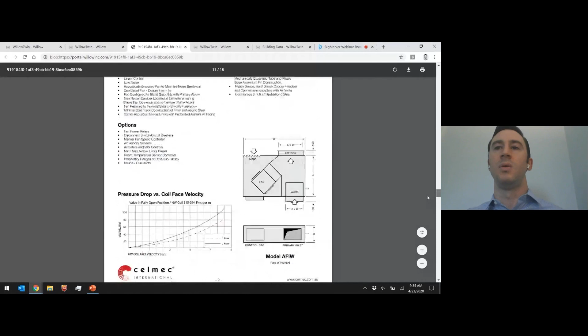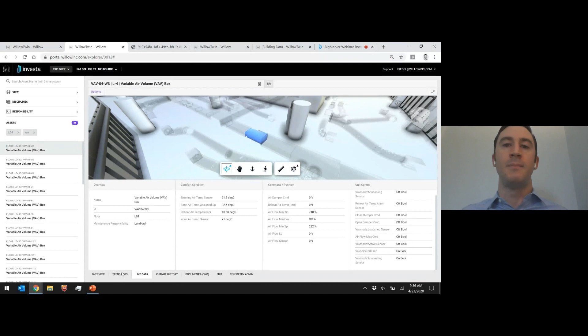We're looking right now at real-time information that comes from the BMS. We're seeing things like the position of the damper inside this VAV box, the speed of the fan, and information about the thermostats that serve this space and ultimately control whether this fan or the VAV is operating in a cooling mode. And we're trending all of that data over time.